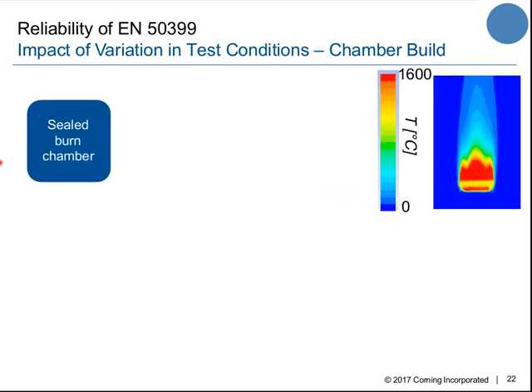The next very important thing to look at is, of course, the temperature distribution of the flame. Air distribution and gas distribution is changing, so probably the temperature distribution is changing as well. So we were simulating this as well and looking at it. Here you see again the sealed burn chamber, and the temperature distribution is very symmetric and very homogeneous. But now I would like you to focus again on the red part here.